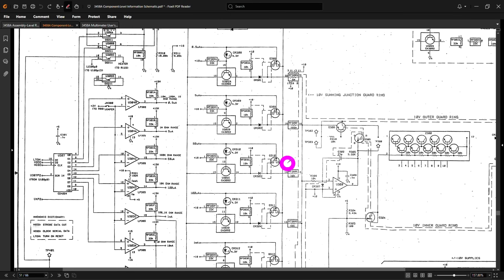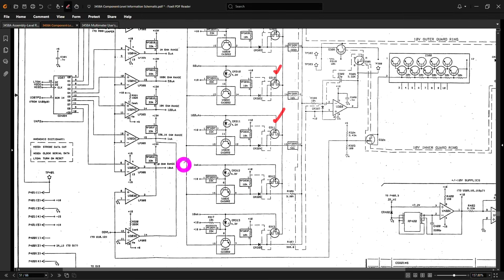So looking back here at the schematic, we can see that we verified the 500 nanoamp current does turn on and off. That one's okay. The 5 microamp signal was okay. 50 was okay. 100 was okay. But then once we got into the 1 milliamp and the 10 milliamp, these signals were not okay. And that could explain the excessive overload condition and the excessive current in the ohms range as well quite nicely.